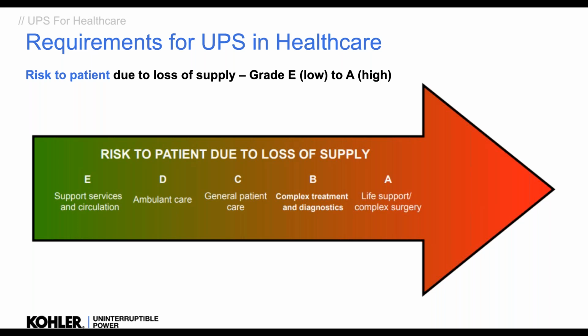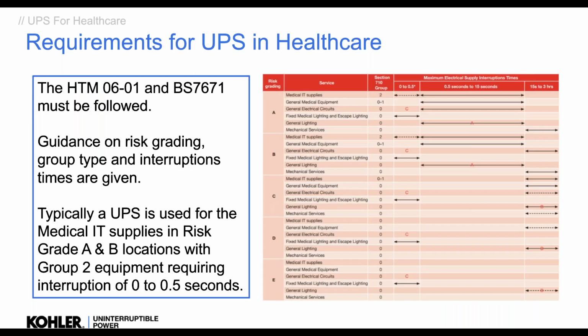And we have the risk to the patient from E up to A, which is the life support complex surgery. So the HTM gives us some guidance of where UPSs should be used, as does BS 7671. And in this guidance, it lets us know where the maximum interruption time is 0 to 0.5. Now that's actually quite a big gap, 0 to 0.5 seconds, because many computers won't run with a 0.5 second gap. So we're looking at 0 for many, many applications now. And to do that, you must have a UPS online in circuit with that kind of situation.